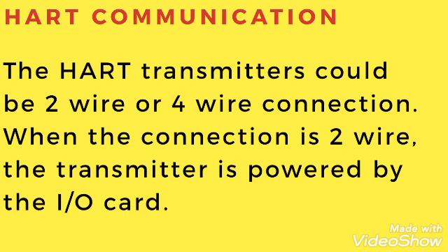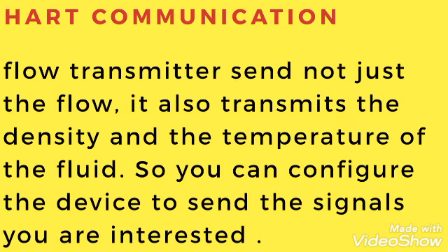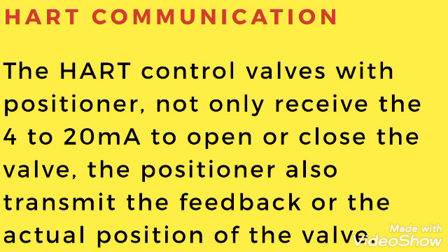The HART transmitter can be a 2-wire or 4-wire connection. When the connection is 2-wire, the transmitter is powered by the IO card. When the connection is 4-wire, the transmitter is powered by an external power supply. A flow transmitter sends not just the flow; it also transmits the density and temperature of the fluid, so you can configure the device to send the signals you are interested in. The HART control valve with positioner not only receives the 4-20mA signal to open or close the valve, but the positioner also transmits feedback on the actual position of the valve.